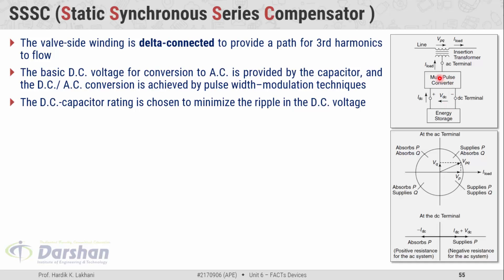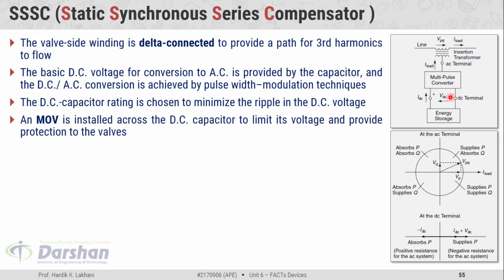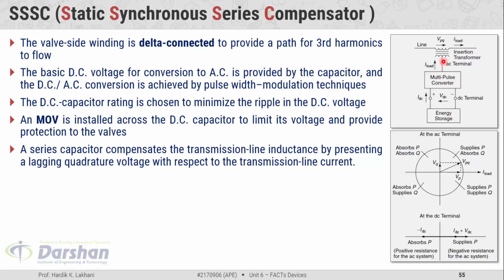While designing the SSSC, the rating of the DC capacitor should be chosen such that when AC is converted into DC using the multi-pulse converter, that DC would contain less ripple. An MOV, also known as the metal oxide varistor, is installed across the DC capacitor to limit its voltage and provide protection to the valves. The metal oxide varistor serves two purposes: limiting the voltage appearing across the capacitor and providing protection to the valves of the multi-pulse converter. In the power exchange diagram, the line current is taken as the reference.